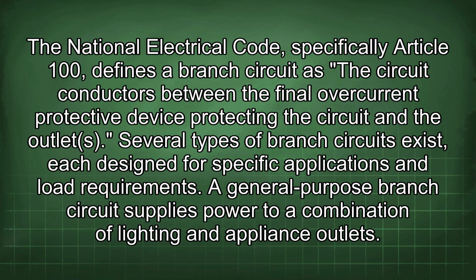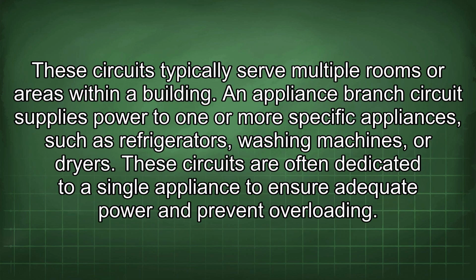Several types of branch circuits exist, each designed for specific applications and load requirements. A general-purpose branch circuit supplies power to a combination of lighting and appliance outlets. These circuits typically serve multiple rooms or areas within a building. An appliance branch circuit supplies power to one or more specific appliances, such as refrigerators, washing machines, or dryers. These circuits are often dedicated to a single appliance to ensure adequate power and prevent overloading.